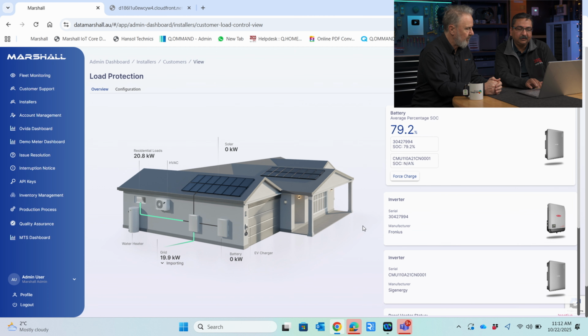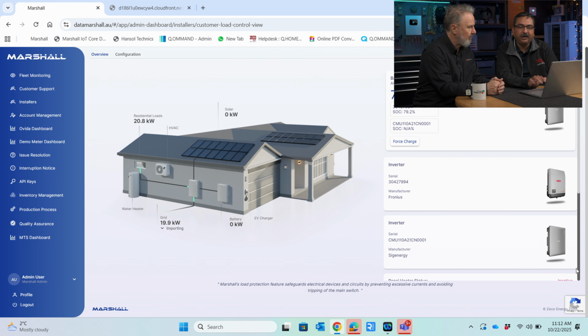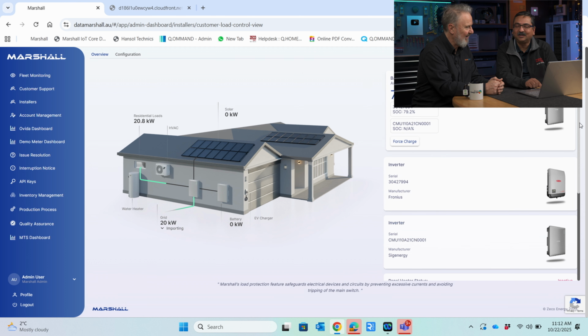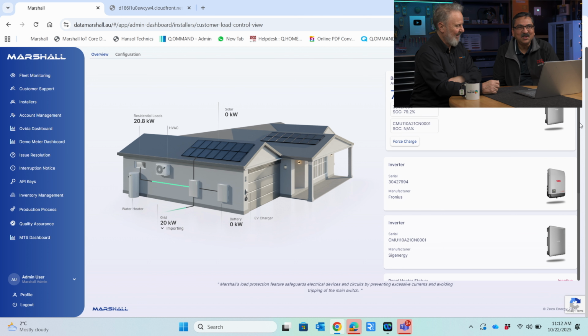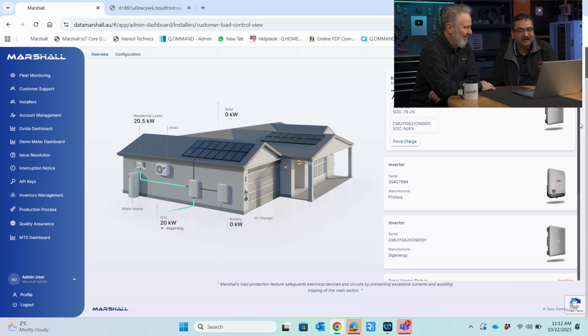I'll scroll down. So the whole site is limited to 40 amps. You've even got my panel heater in here. Yes, the panel heater is there as well, which you use as a dump load. So we've got that one too, and we turn the load on and off under this threshold.